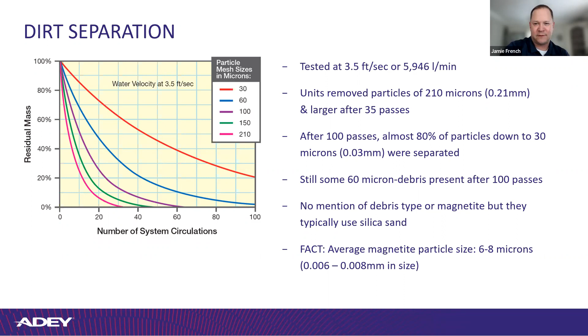So air and dirt separators are typically on the supply side of the system. Manufacturers are now starting to add a magnet to this device as a sort of check-the-box hat tip to it. But again, they're relying on separation and not capture. A lot of times these magnets will be on the bottom and not necessarily in the flow. I guess if there's a pressure drop there, it might work its way down, but most of that stuff's whistling straight through.